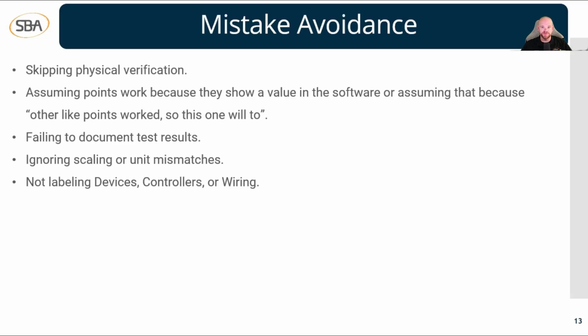The next one here, I've been guilty of this one in the past. Wish I never did because it caused me some heartache in the field as well. But assuming points work because they show a value in the software, or assuming because that point is just like other points, it'll work. Or just because this point was like the other point that worked, this one will too. That's a really, really bad way to be. And again, I admit I've done that in the past as well, just because time constraints, deadlines, that's still not an excuse. You need to make the time to make sure that you're verifying all this stuff. Okay, don't make the excuses.